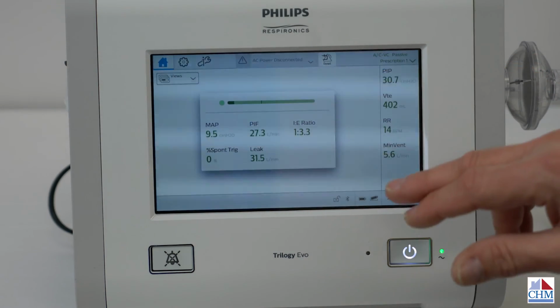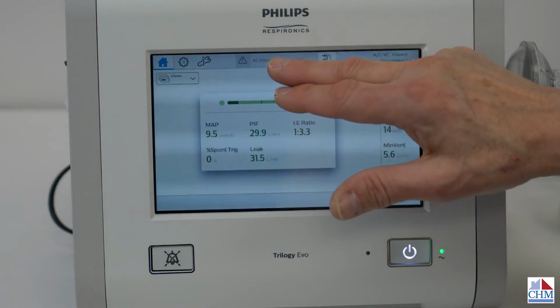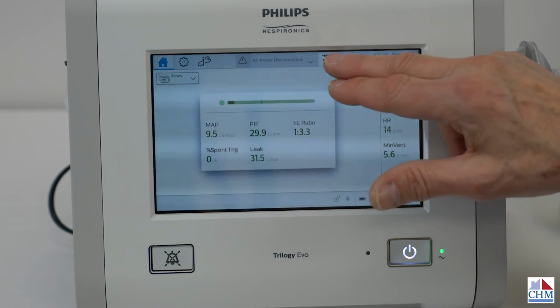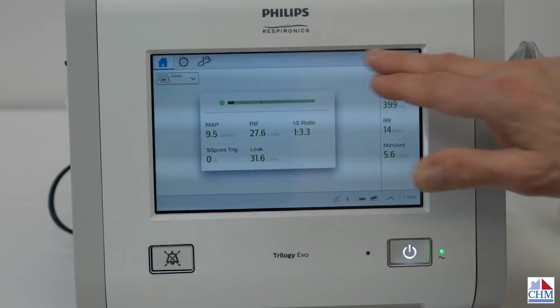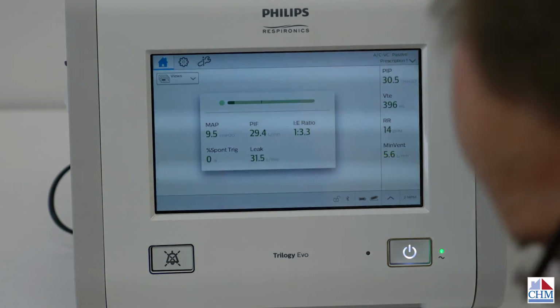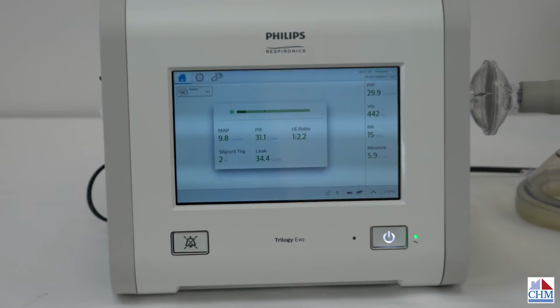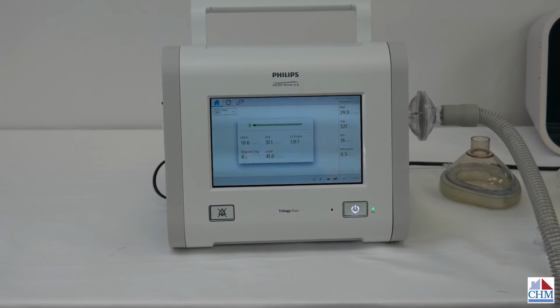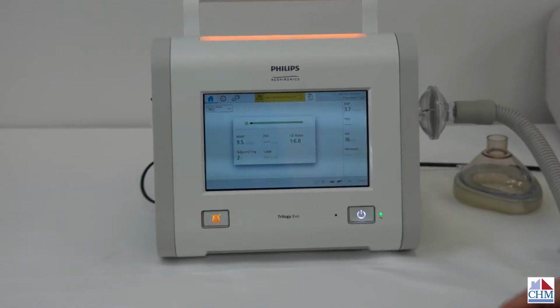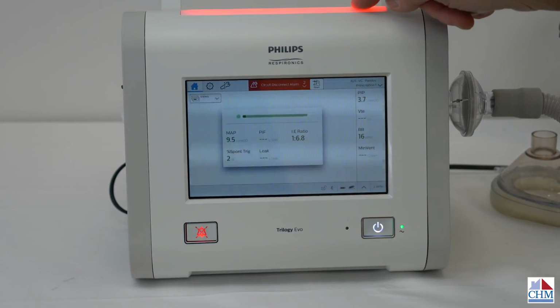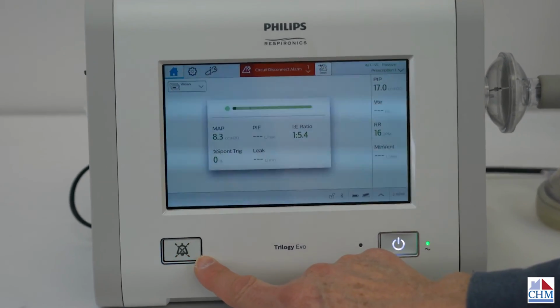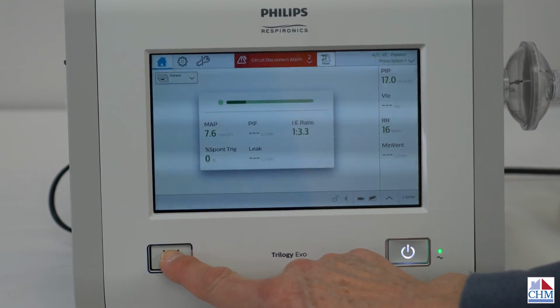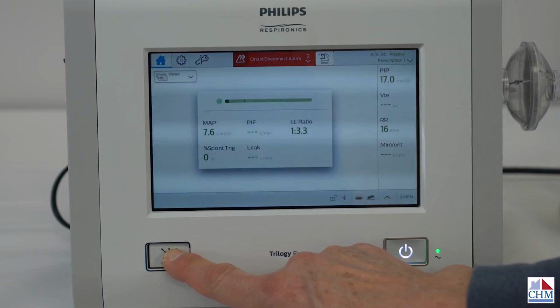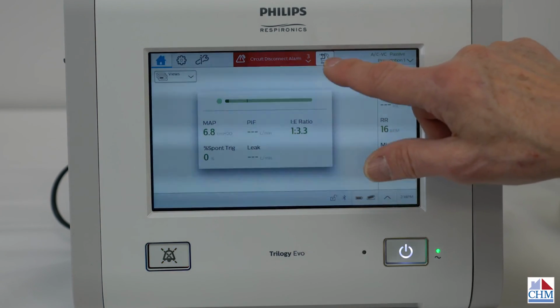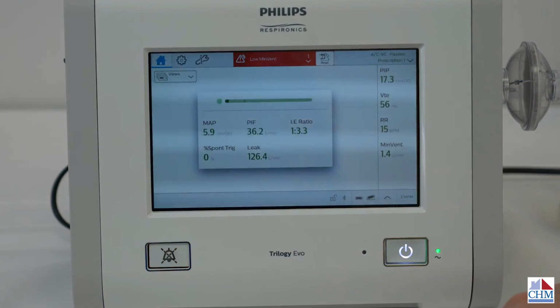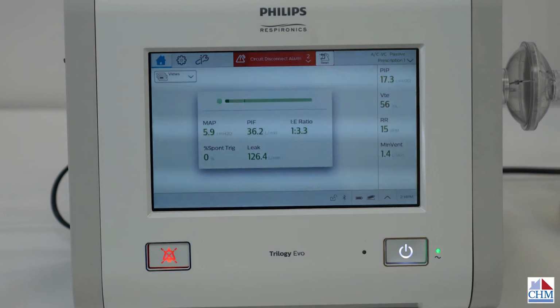Any alarms, let's say we have an alarm on the ventilator, clearing it, like right now we have AC power disconnected. I'll just hit this to reset it, and that clears that display. The alarms that show up, if I were to cause an alarm here, I'll disconnect our test lung so we can get an alarm on our vent. You would get an audible alarm, and we get the light bar along with the flash here. I can temporarily, if I hit audio pause, turn off the audible, and then I can also hit reset here to clear it. And it'll come back on again, of course, because we still haven't corrected the problem.